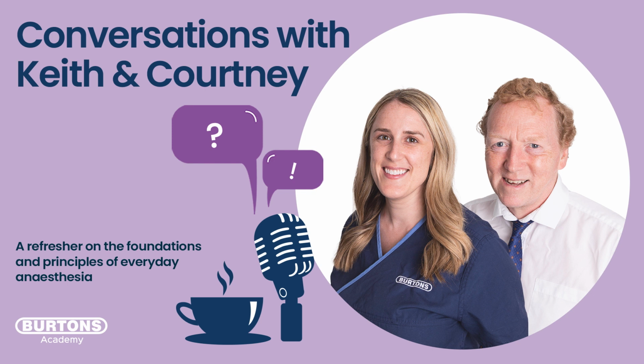Or just check for bubbles in your airways. Check for poor junctions, that you haven't got a problem where you've got your arc line connected to your catheter or connected to the transducer, because if they're loose and they're leaking, that's going to affect that. That's going to overdamp it as well. So that's what you see about those terms, overdamping and underdamping, and that's how you test them.